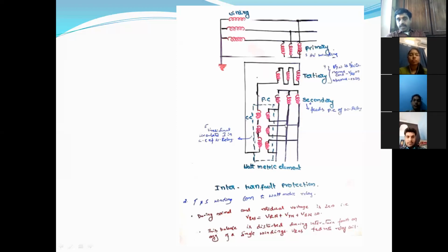So for the relay to operate, because this is the secondary of the 3 winding transformer, it feeds the pressure coil of the wattmetric relay. Whenever there is a residual voltage, there will be a current in the current coil, then the wattmetric relay will operate. Therefore, it trips the circuit breaker. So this balance is disturbed. That means the 3-phase voltage balance is disturbed during an interturn fault on any of the single windings. The V residual is fed into the relay.